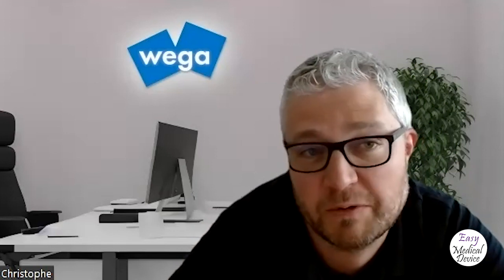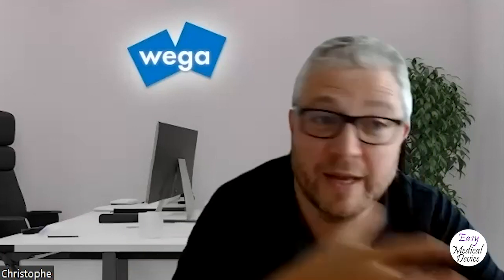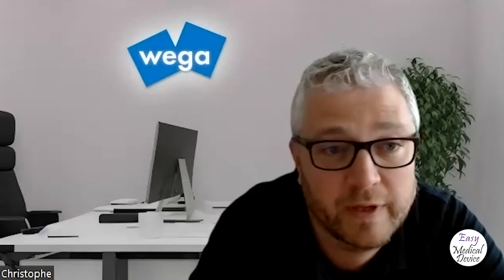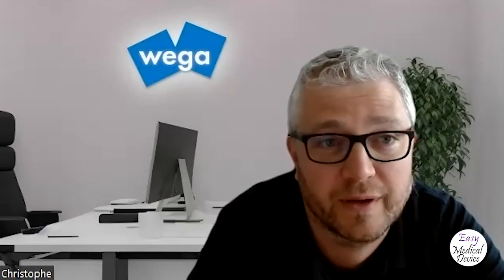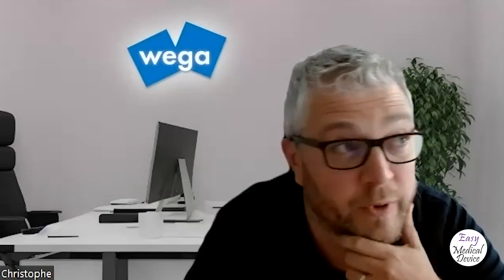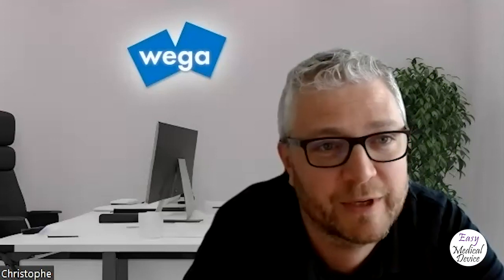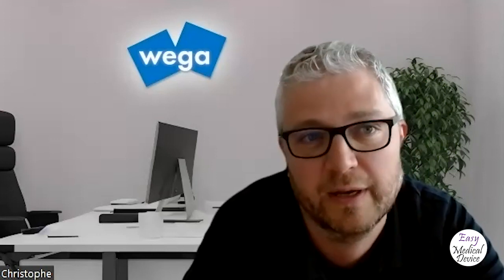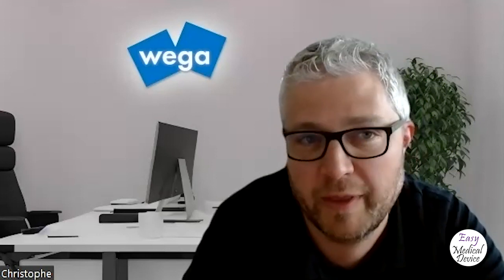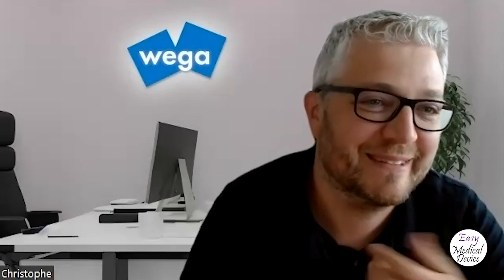After you first validate it, you introduce what you call change management, which we are used to more on the medical device product itself, but also for the quality tools you need change management in place to review any modification and to ensure that you follow the procedures, because introducing such a system means also defining how I maintain it and how I manage it. For example, how do users get access? This is a classical issue. Can anyone, just because he's the best friend of the system administrator, suddenly become an admin in the system? That should not be the case.